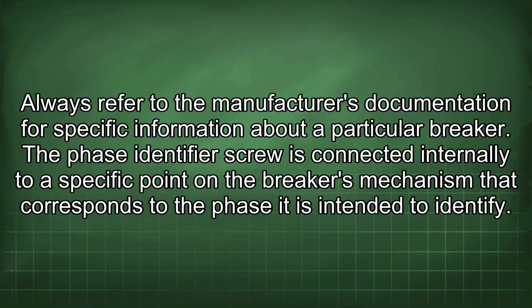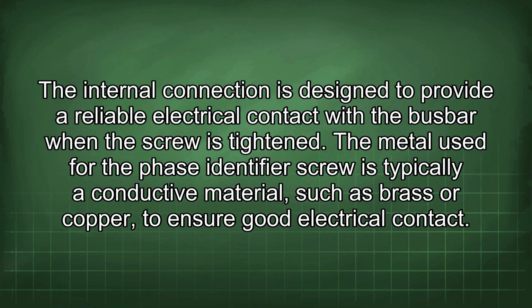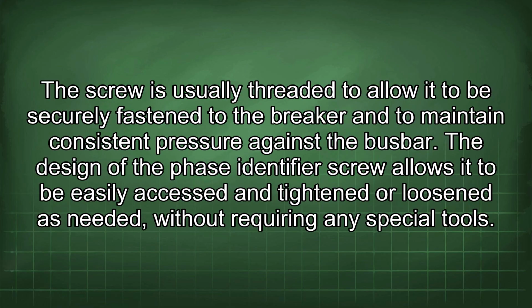The phase identifier screw is connected internally to a specific point on the breaker's mechanism that corresponds to the phase it is intended to identify. The internal connection is designed to provide a reliable electrical contact with the busbar when the screw is tightened. The metal used for the phase identifier screw is typically a conductive material, such as brass or copper, to ensure good electrical contact. The screw is usually threaded to allow it to be securely fastened to the breaker and to maintain consistent pressure against the busbar.